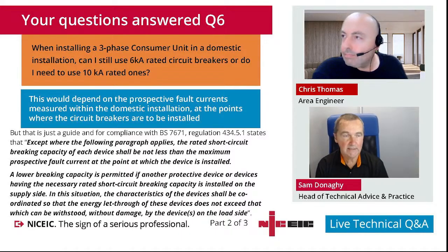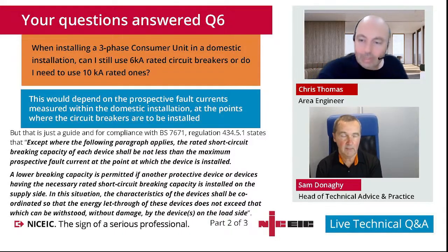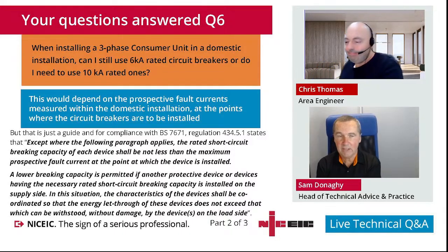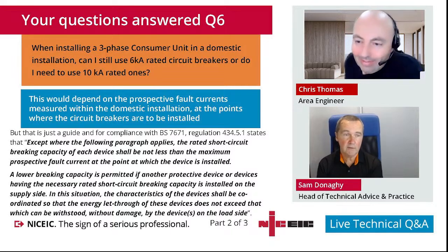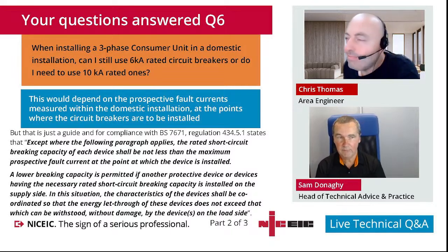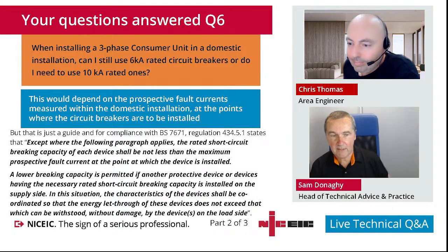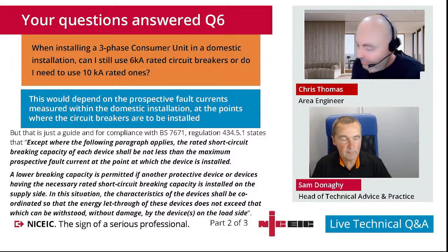rating. Obviously, you can use a 16 kA rated device anywhere where it's acceptable to use a 6 kA, because it's got a higher rating. It would probably not be economic to do that, but you could do it. What you can't do is use a 6 kA rated device where you need a 16 kA because of those higher potential currents, fault current, short circuit, and potentially earth fault that the protective device may need to deal with and still be able to operate after it's been reset.